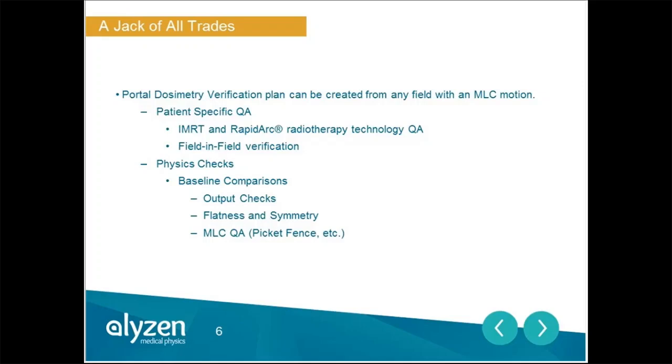That we can do things like output checks, for example. We can verify flatness and symmetry once we set a baseline. We could do picket fence evaluation.